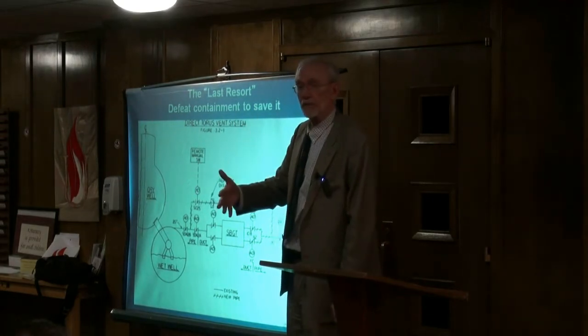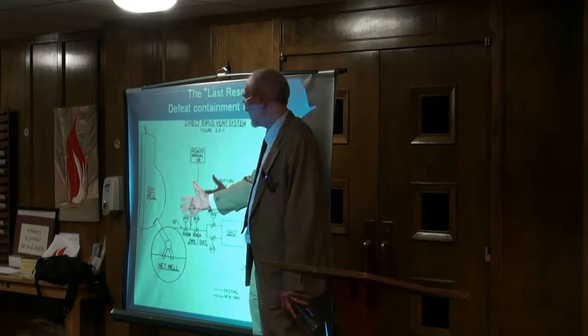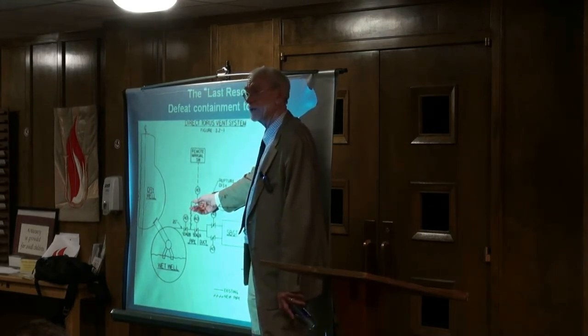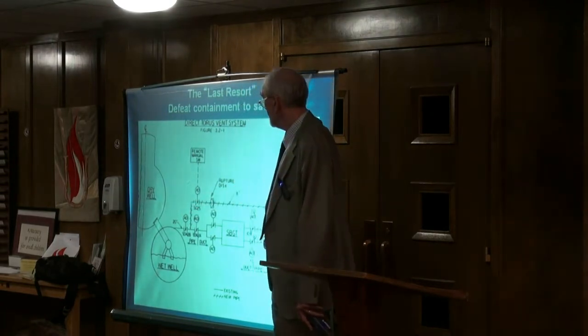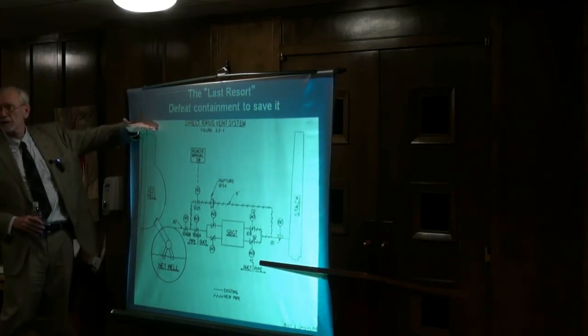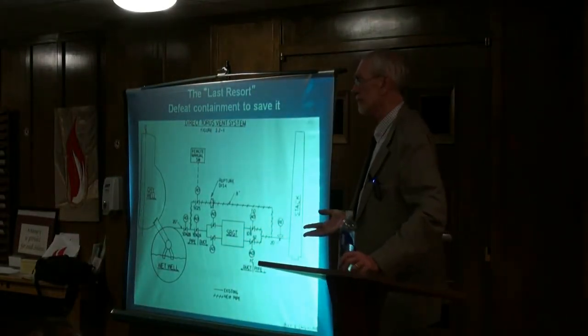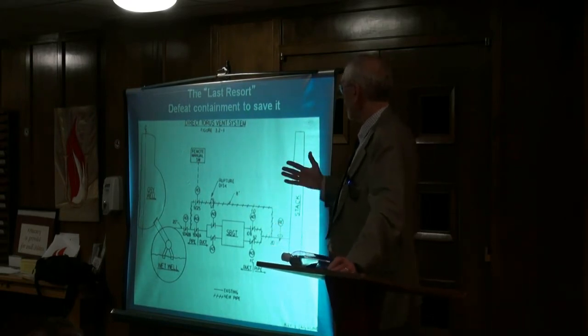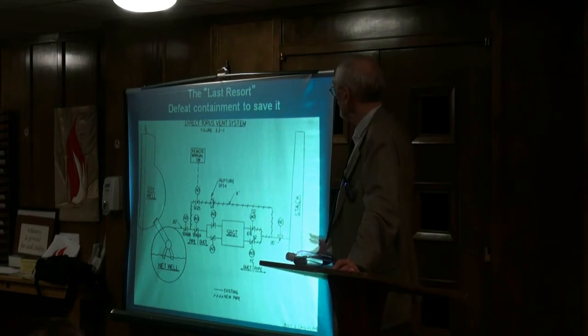With the total power failure, this vent would not open. The radiation was too high for workers to get in there to manually open. And hydrogen gas, at this point, hydrogen gas has lifted the top of this component off its screws. And hydrogen gas is now getting into the reactor building, where in all cases it found ignition points. And we saw the detonations that we've been warned about since 1972 and have been completely ignored. Next slide.